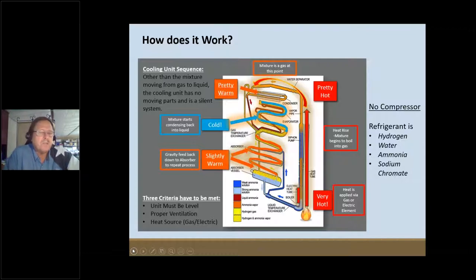Then we take it through what they call a condenser — the same thing as a radiator on an automobile. We run the gas through the condenser on the inside of the tubes and run air across the outside of the tubes and fins to exchange that heat and move it on. If we do not get rid of that heat, we cannot go get more heat from the freezer and refrigerator. Even though they have no moving parts, these units still require maintenance.